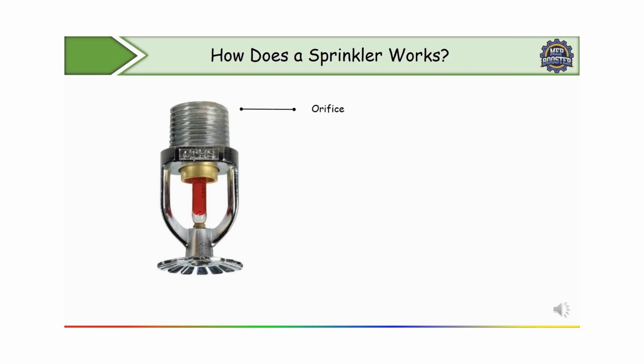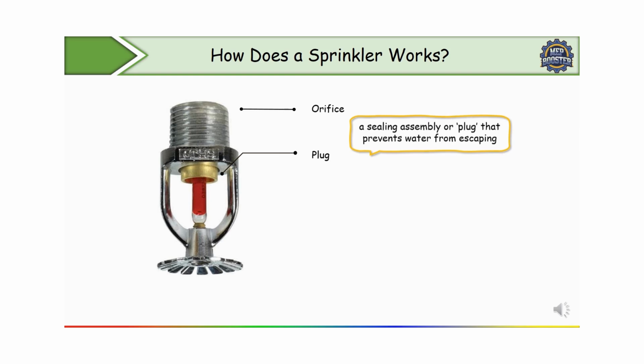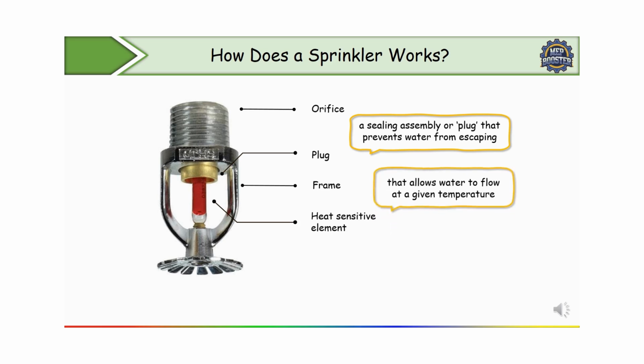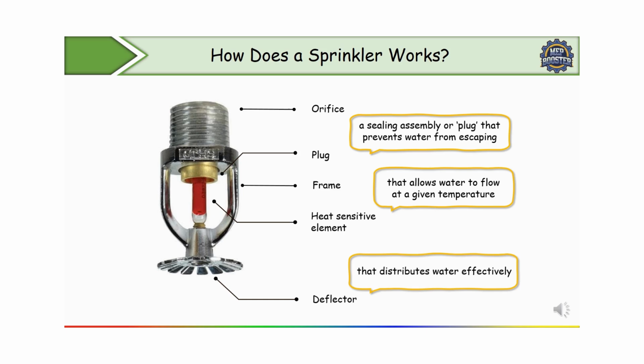Now if you see here, the sprinkler head is shown. Here the orifice is given, with plugs. Plugs are what? A sealing assembly or plug that prevents water from escaping. The frame is also shown, holding the heat sensitive elements that allow water to flow at a given temperature, and the deflector is shown, which distributes water effectively. So these are the parts of the sprinkler head. Now we'll see how a sprinkler works.